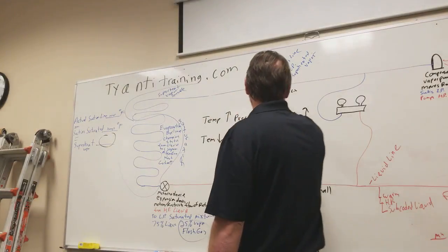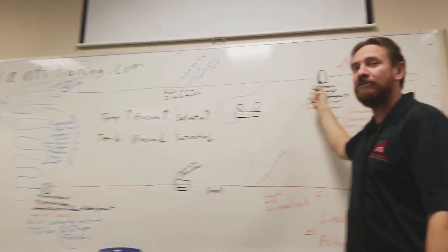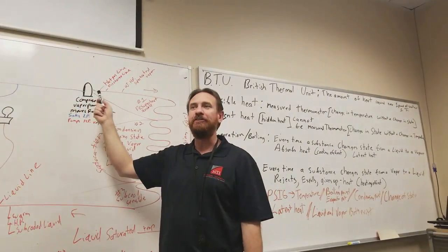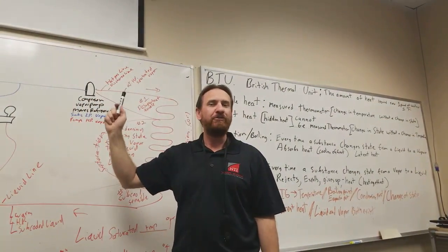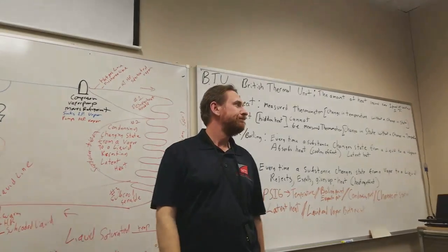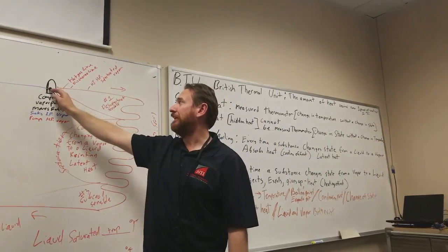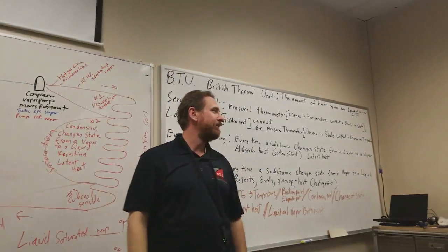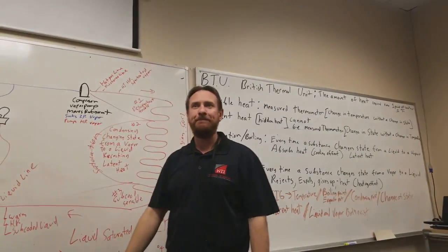Now I start getting liquid coming back to my compressor. And while I solve the problem today, I am killing that compressor. The compressor will die sooner or later. Eventually the compressor will get liquid, and you try to compress a liquid and it just snaps and it will break. Something will break. Yep. And it happens a lot.